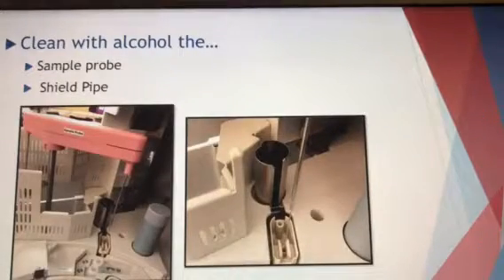The next thing is we're going to clean the sample probe and the shield pipe with an alcohol pad. And the sample probe, you can see in the first picture there, it's connected to the pink part that you see there, and it's a probe that drops down. And you're just going to swipe over that with an alcohol swab. And then the shield pipe, you can actually see it in both pictures, but a close-up picture is in the second one. And just clean inside of that with an alcohol pad, and just be very careful not to drop one down in there. That would not be good.